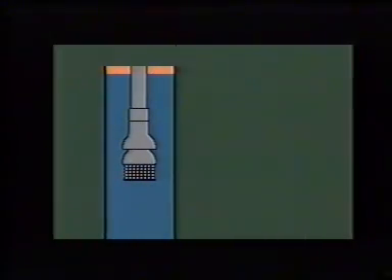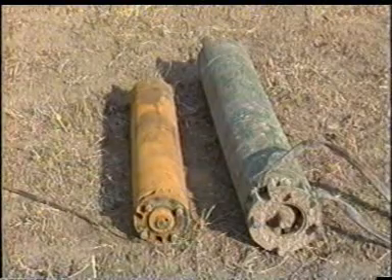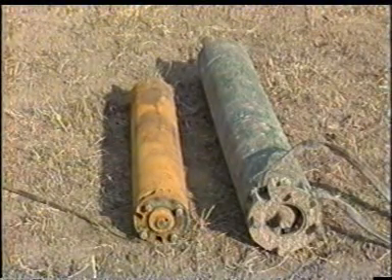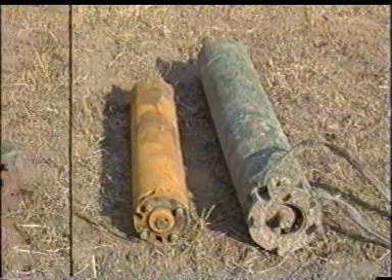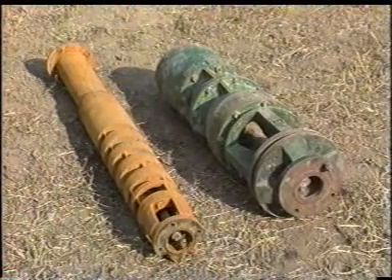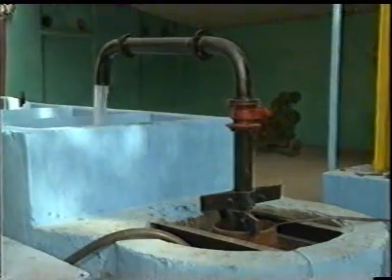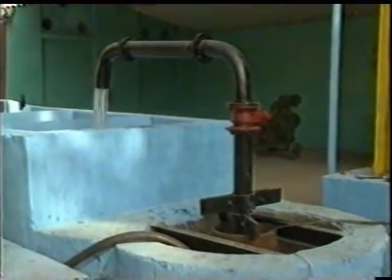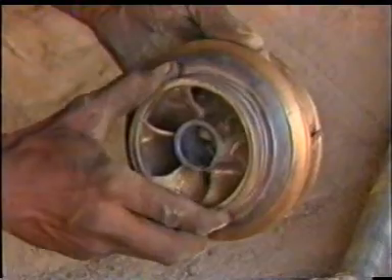And in some cases, by adding additional stages and using a larger motor in addition to lowering of bowls. If required, the pump size is reduced. Decline in pump discharge and head may be due to defects of pump or both well and pump.